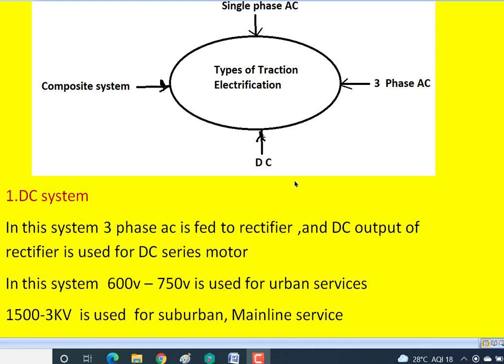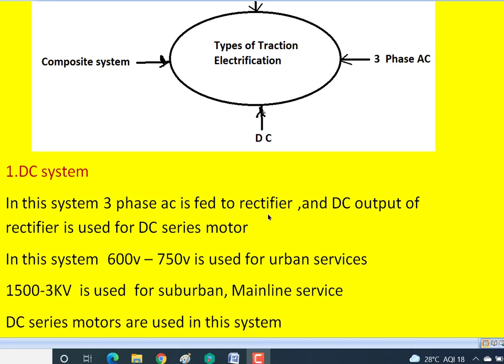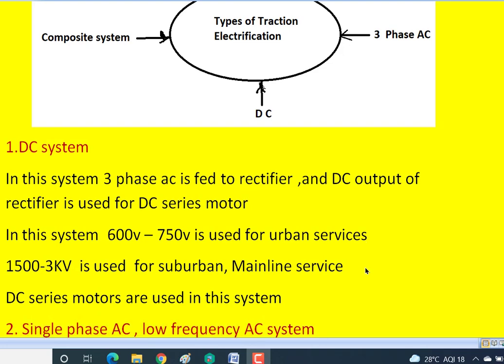Let me consider them one after the other. In the DC system, a 3-phase AC supply is fed to a rectifier, and the output of the rectifier is used to drive the DC series motor used in the traction system. For urban services, the voltage range used is 600 to 750 volts, whereas for mainline and suburban services, the voltage used is between 1500 volts and 3 kV. The motors used in the DC traction system are DC series motors.